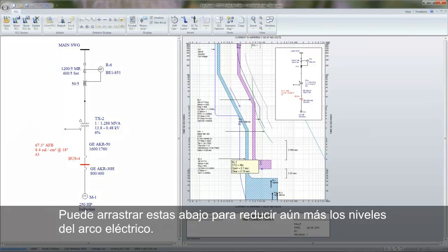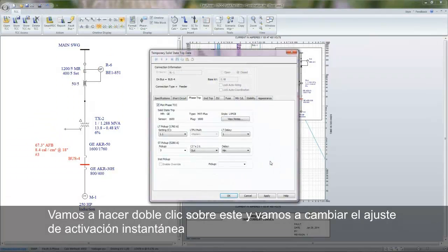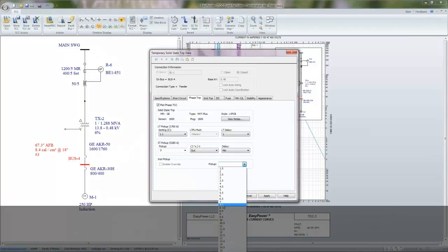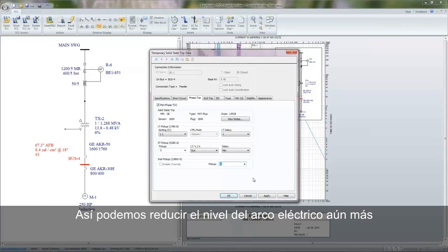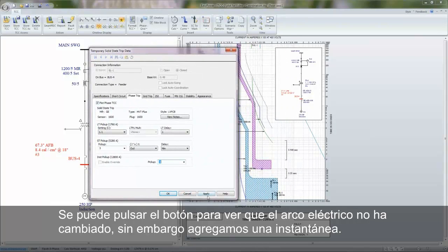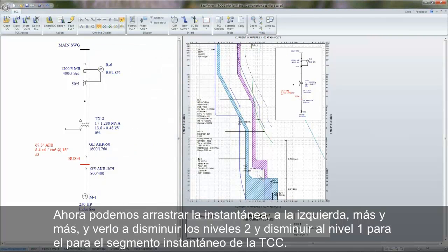You can drag these down to reduce the arc flash level even further. We're going to double click on this, and we're going to change the instantaneous pickup setting so we can reduce the arc flash level further. We can hit the apply button and see arc flash hasn't changed, but we added an instantaneous. Now we can drag the instantaneous left further and further and watch it decrease to level 2 and decrease to level 1 for our instantaneous.